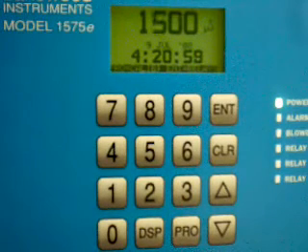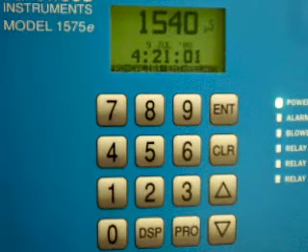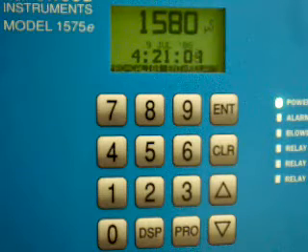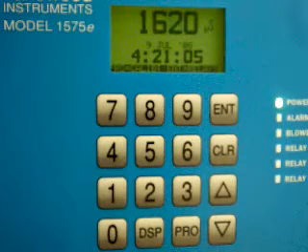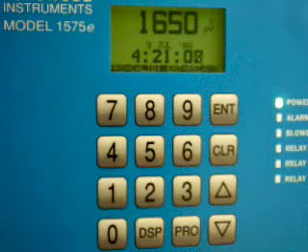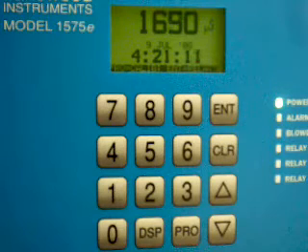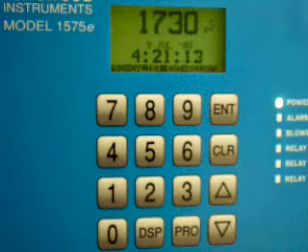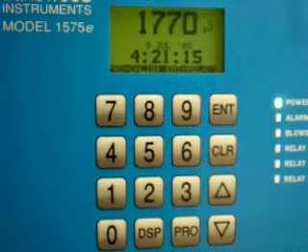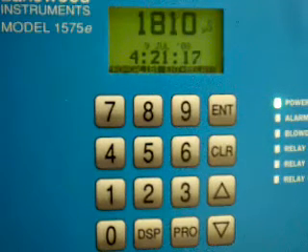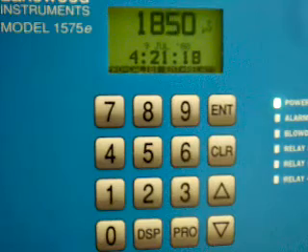Now, for example, if someone's messed with the calibration and has entered information incorrectly and kind of chased calibration, you may have created a situation where you go to calibrate and it never seems to line out anymore. It always seems to be slightly off. Well, to clear out that junk information, you can initialize the calibration only.